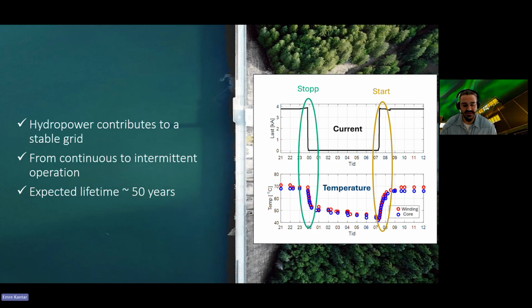What happens during a start and stop is that if the stop period is long enough, the machine, windings, and core temperature can drop quite a bit before it starts again. We have some gradients and time constants associated with all of this, and they affect the lifetime of a generator.